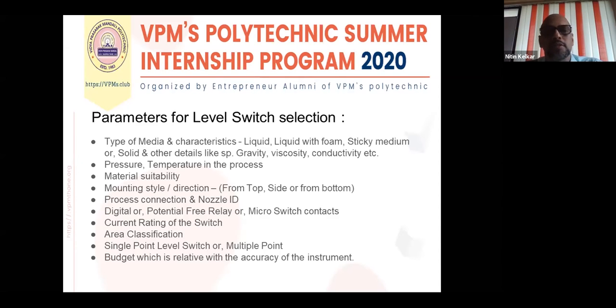Then, potential free contact switch, you mean there can be different types. It can be a digital switch or it can be a potential free contact. In potential free contact, there is again either a relay or a micro switch. So it all depends upon the electrical load. What are you going to operate with this switch? Are you going to operate some 3-phase pump, or just an LED, or a buzzer, or a hooter? It can be anything. So depending on the current load, accordingly the type of switch has to be selected.